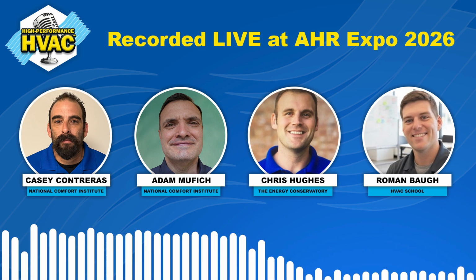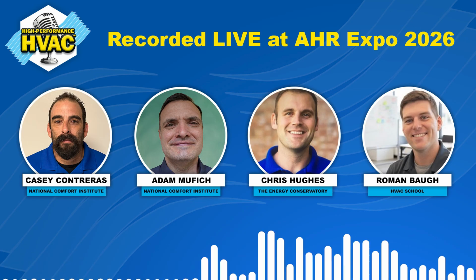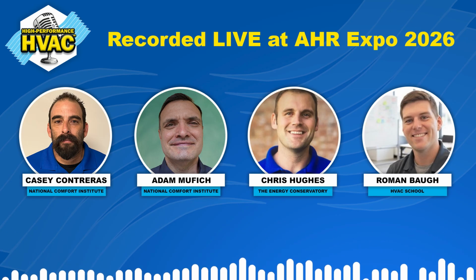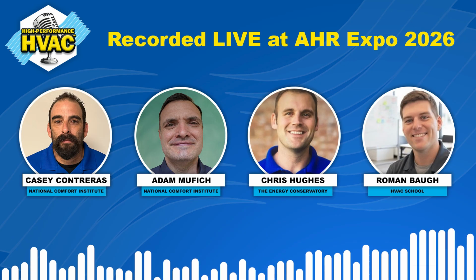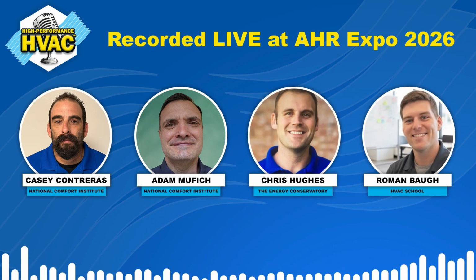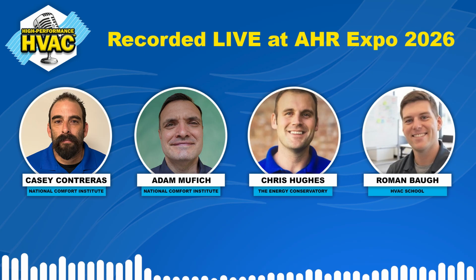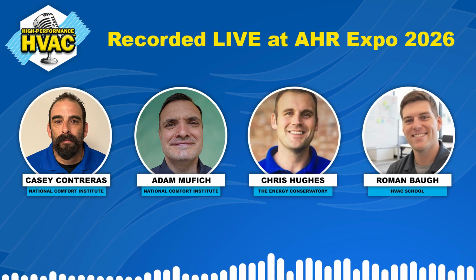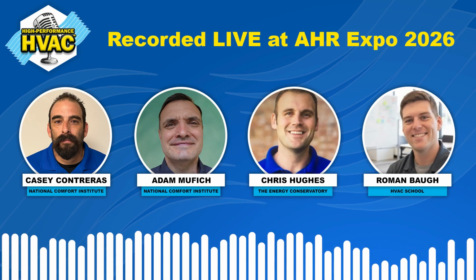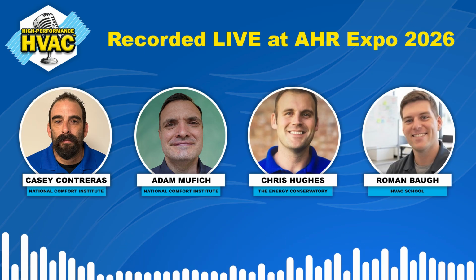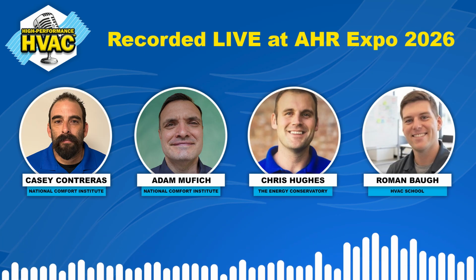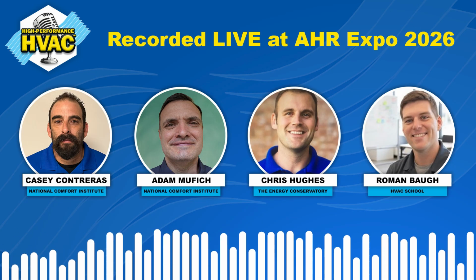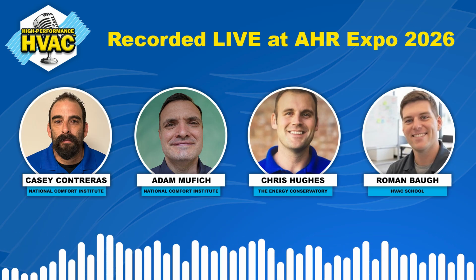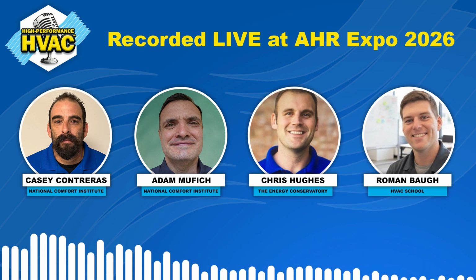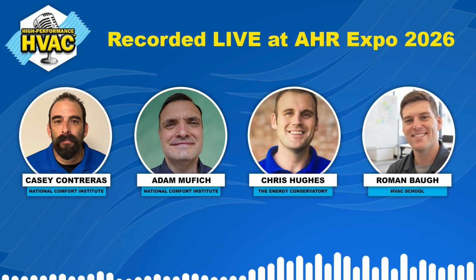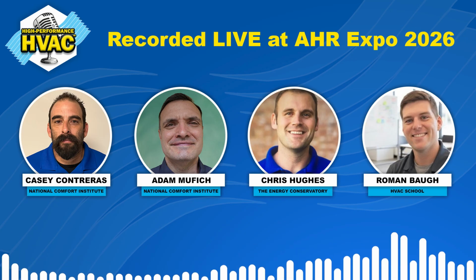Discharge superheat. So discharge superheat is the quality of compression leaving the compressor. In suction superheat, I want to make sure that we're measuring the superheat on the suction line, so there's no liquid coming back, right? The purpose is, am I getting good heat exchange, or am I picking up way too much heat? Am I not doing enough vapor? That's suction superheat. We measure the same exact thing on the leaving side of the compressor to measure the quality of compression, discharge superheat. And they usually go hand in hand. So if my suction superheat is high, and my discharge superheat is high, it's because I don't have enough vapor coming into the compressor.